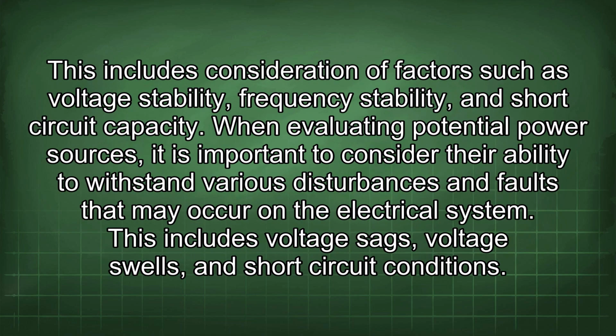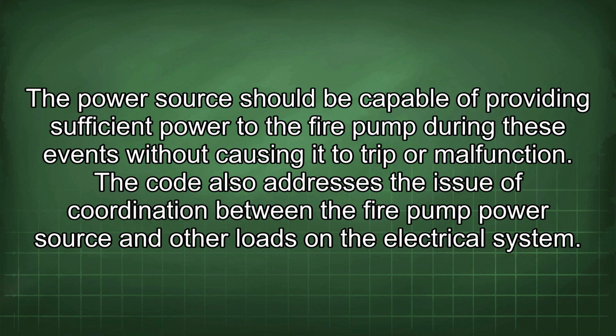This includes consideration of factors such as voltage stability, frequency stability, and short-circuit capacity. When evaluating potential power sources, it is important to consider their ability to withstand various disturbances and faults that may occur in the electrical system. This includes voltage sags, voltage swells, and short-circuit conditions. The power source should be capable of providing sufficient power to the fire pump during these events without causing it to trip or malfunction. The code also addresses the issue of coordination between the fire pump power source and other loads on the electrical system.